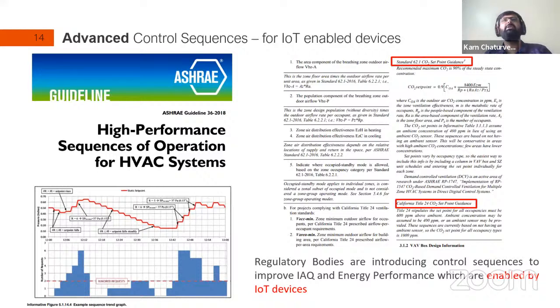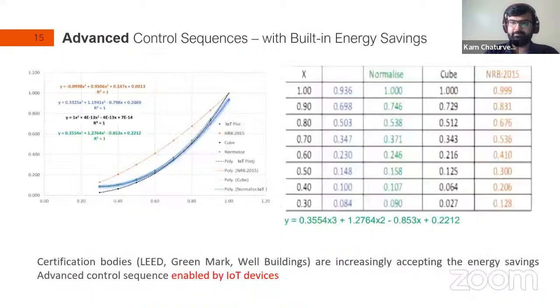Because these control sequences are no longer limited to, say, controlling based on a group of static set points or return or supply temperature - they actually want input coming in from various zones. And based on that input from various zones, they want the system to respond in an aggregated manner. So the expectation is that your control sequence should also be able to parse and apply a whole lot of data and control accordingly.